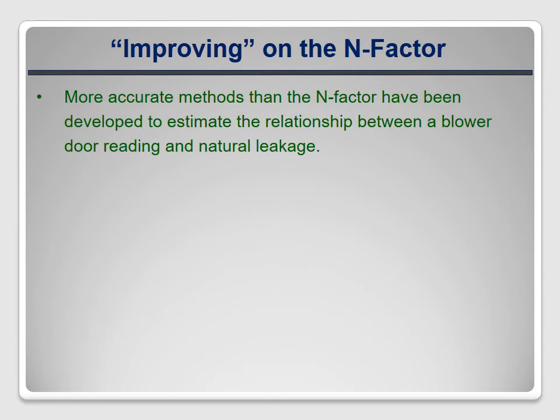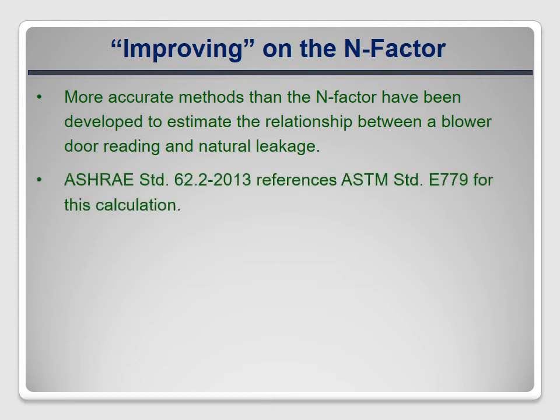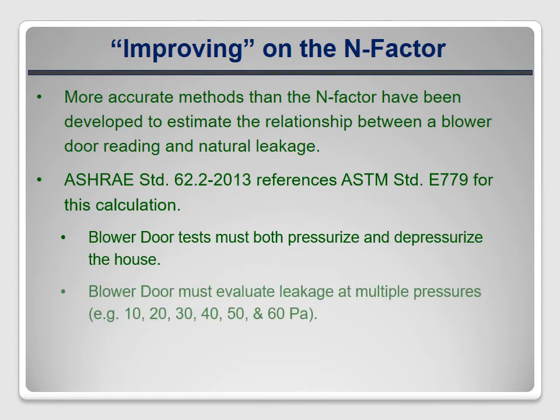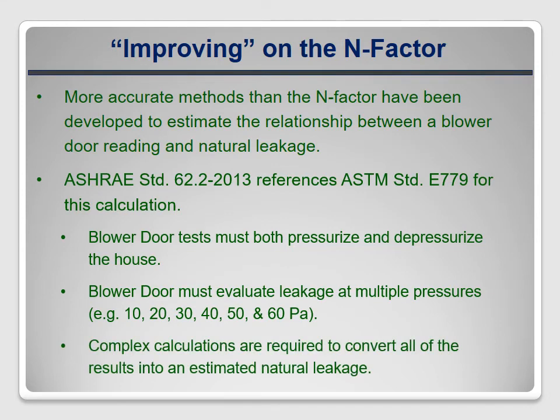ASHRAE 62.2 2013 references the calculation methods in ASTM standard E779. The blower door test must be done in both pressurization and depressurization, and it must be a multi-point test ranging from 10 to 60 pascals. All of that data must be crunched down to get a single number estimating the effective leakage area of the house. The sample calculations take up four pages in ASTM 779 — that's more work than can be justified on each house, not to mention the challenge of making sure each auditor knows how to do it all correctly.